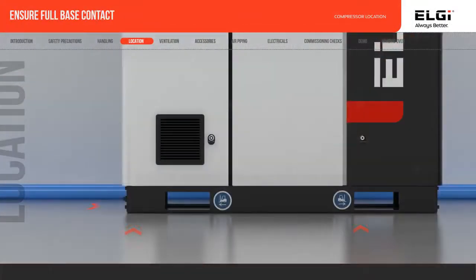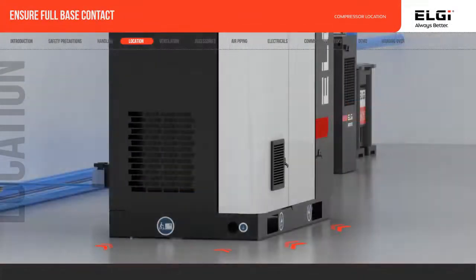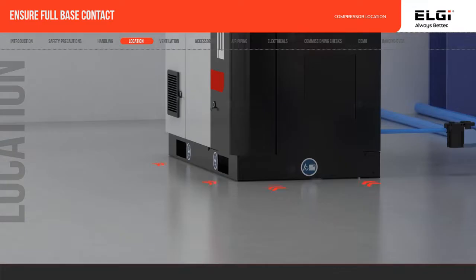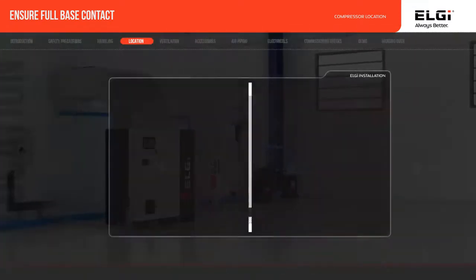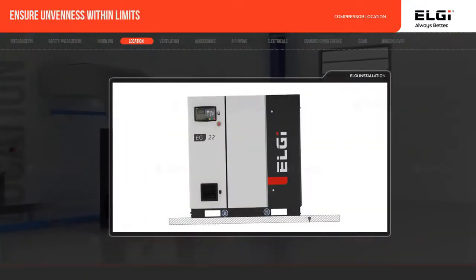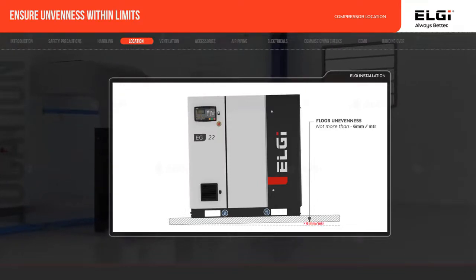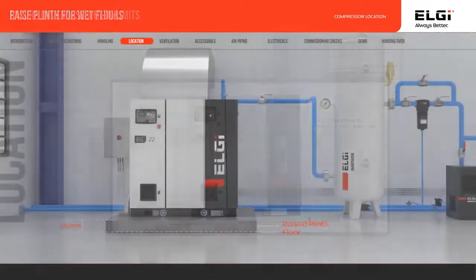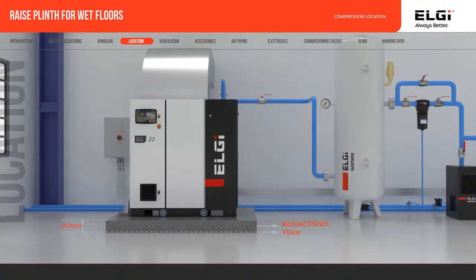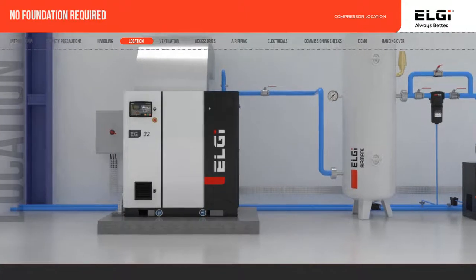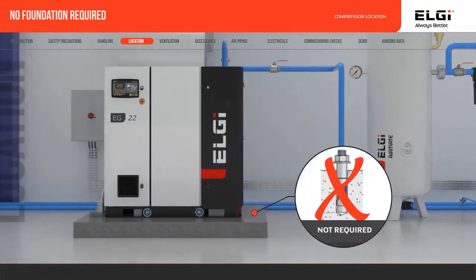Ensure the compressor base makes 100% contact directly with the floor. Ensure unevenness of the surface is within 6 mm per meter. If the floor is splashed frequently with water while cleaning, then place the compressor on a raised concrete plinth of 150 mm. Special foundation is not necessary for rotary screw compressors.